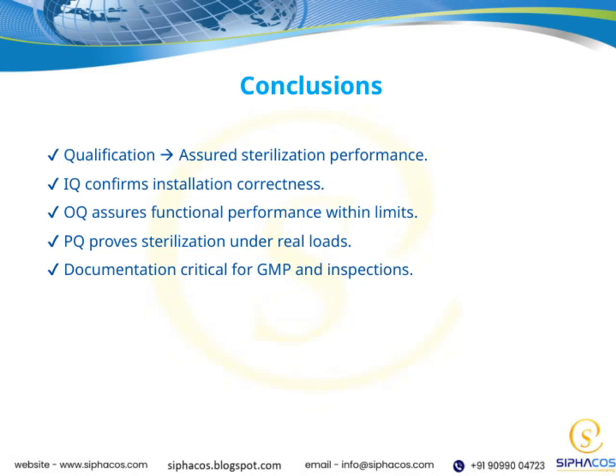So, in conclusion, let's reflect on the key points we've discussed. First, qualification is essential because it assures us of sterilization performance. When we qualify a system, we're confirming that it consistently meets the required standards. Next, IQ, or installation qualification, helps us verify that everything has been installed correctly. This is fundamental to ensuring the system functions as intended right from the start. Moving on, OQ, or operational qualification, takes us a step further by assuring that the equipment performs within established limits during normal operation. This is crucial for maintaining consistent quality.